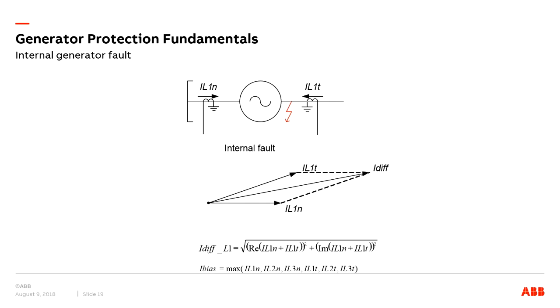So as you can see, in the event of an internal fault, the differential current is going to be much higher, and the ratio between the differential current and the bias current is larger than 1, which makes the differential protection operate. So this will happen only in the event of an internal fault.